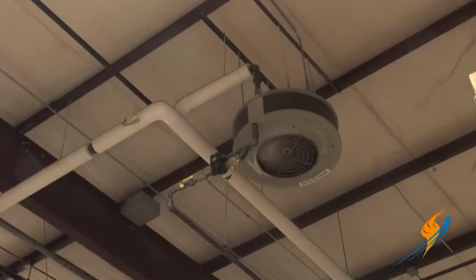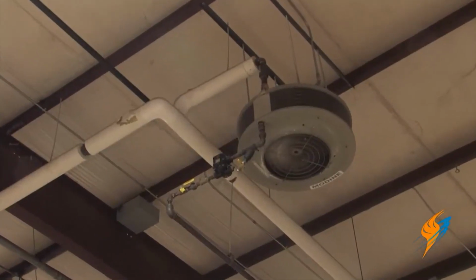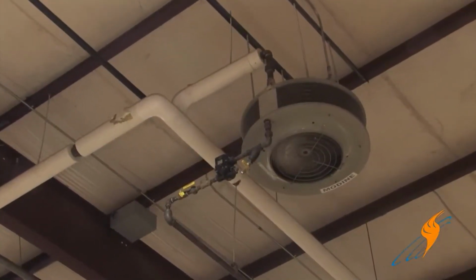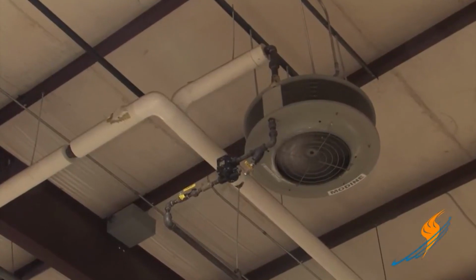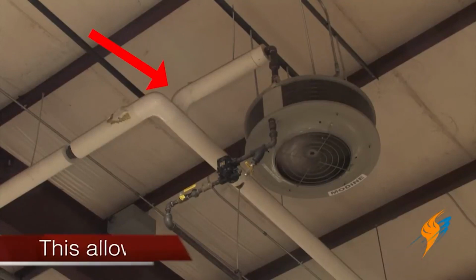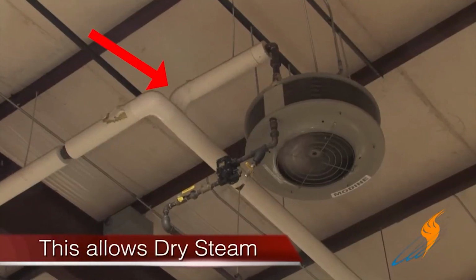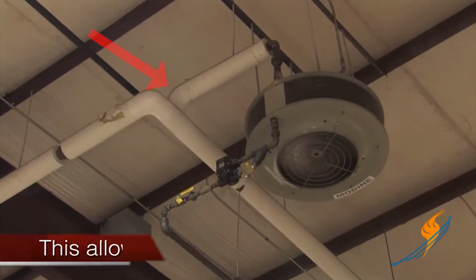This is a nice example of a nicely installed unit heater. As you can see, the steam supply piping to the unit heater comes out of the top of the supply header, and that ensures that you get dry, clean steam to the unit heater.